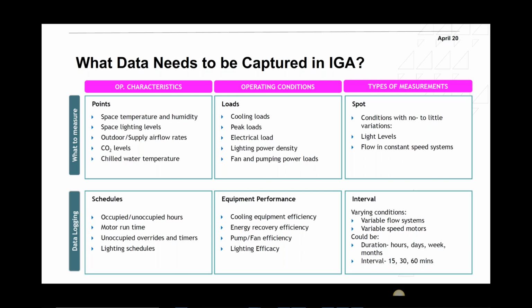Chilled water temperature, supply and return, to see if they have any low delta T issues. Operating conditions like loads, cooling loads. I can put a BTU meter on the chiller to check what the cooling load is. I probably would put it there for a month if I can. What are the peak loads? Electrical load. I can put the power analyzers on the MDBs or the MCCs or any kind of equipment I need to take measurements of. Lighting power density. Taking the watts per square meter in a specific room, I can compare it to 90.1 to see if I am above or below the standard requirements. Fan and pumping power loads.